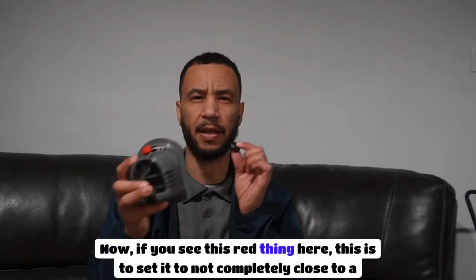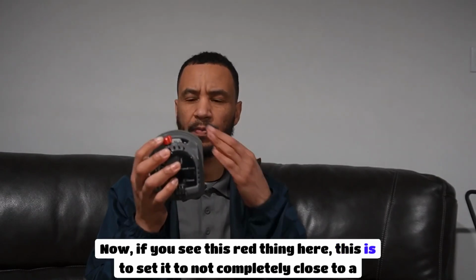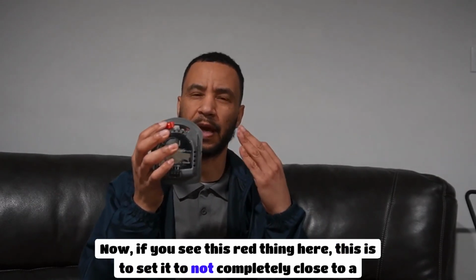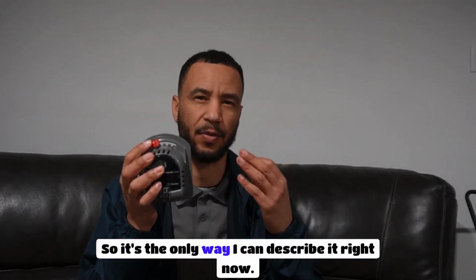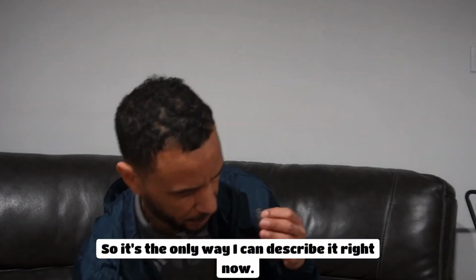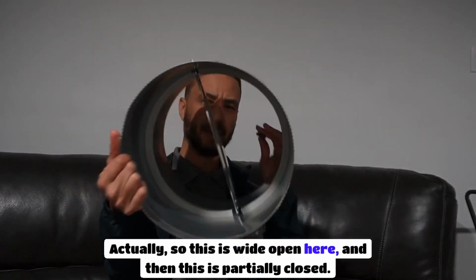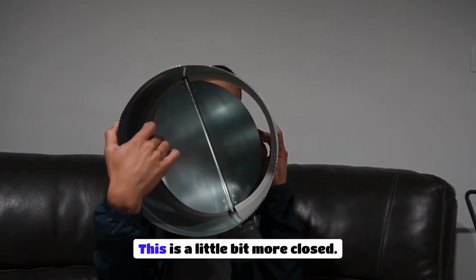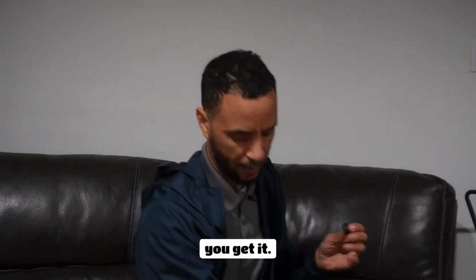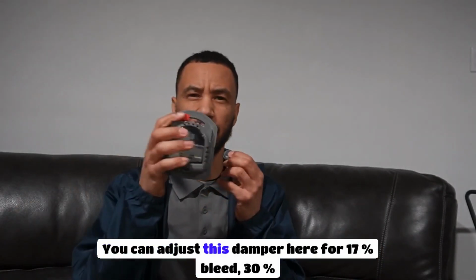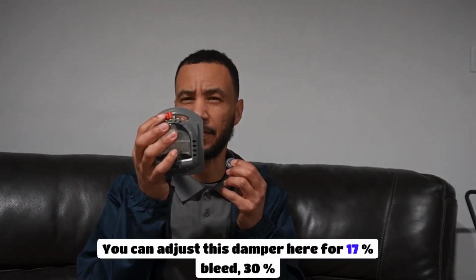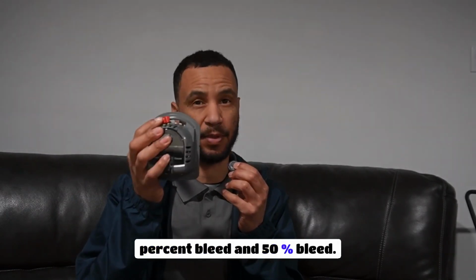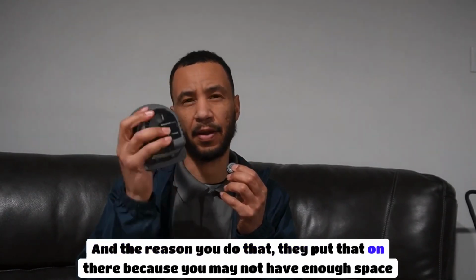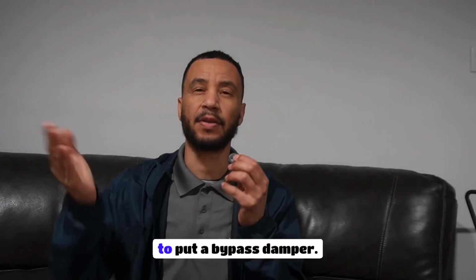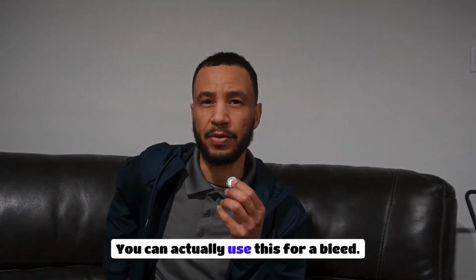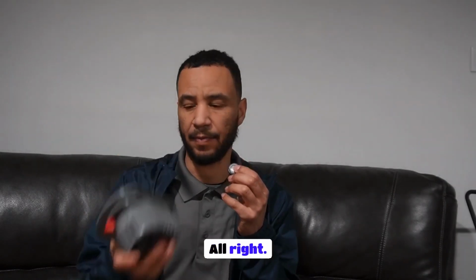Now, if you see this red thing here, this is to set it to not completely close to a certain extent. All right, so it's the only way I can describe it right now. Actually, so this is wide open here. And then this is partially closed. This is a little bit more closed. So you get it. You can adjust this damper here for 17% bleed, 30% bleed, and 50% bleed. And the reason you do that, they put that on there because you may not have enough space to put a bypass damper. You can actually use this for a bleed. All right.